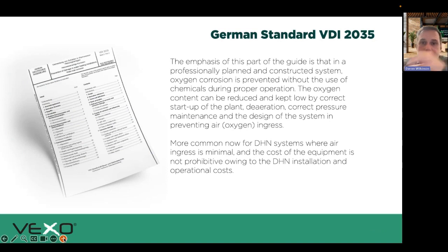I said I'd touch on the German VDI standard. It works if it's a professionally planned and constructed system. If you're looking to deploy the VDI standard and avoid use of chemicals, that's a great idea if we can do it, but you need to make sure right at the front end that you're designing that system appropriately, because it relies on you having no ingress of oxygen at all. It can handle some, but too much water loss will ultimately impact the equipment.